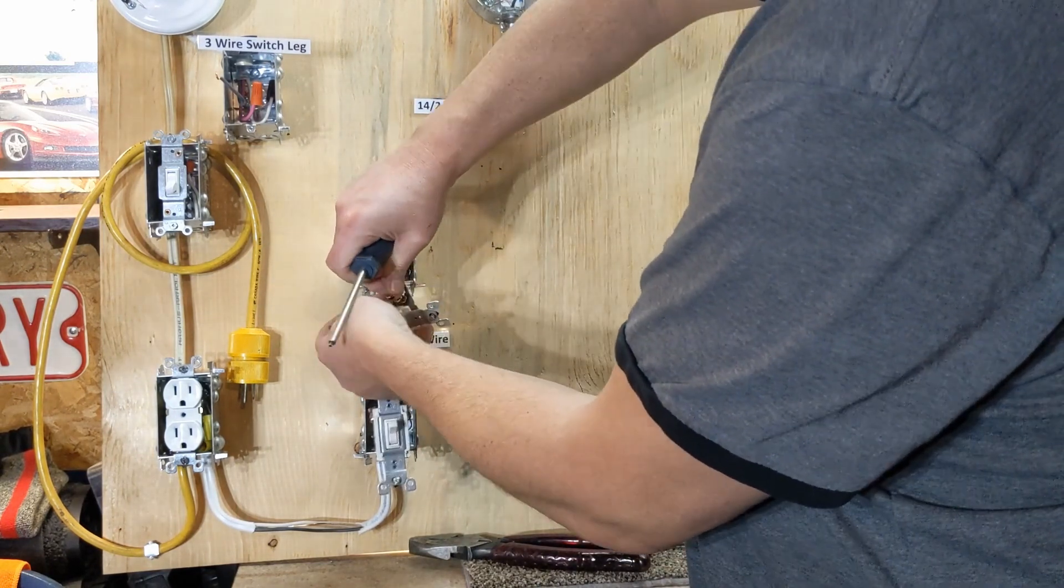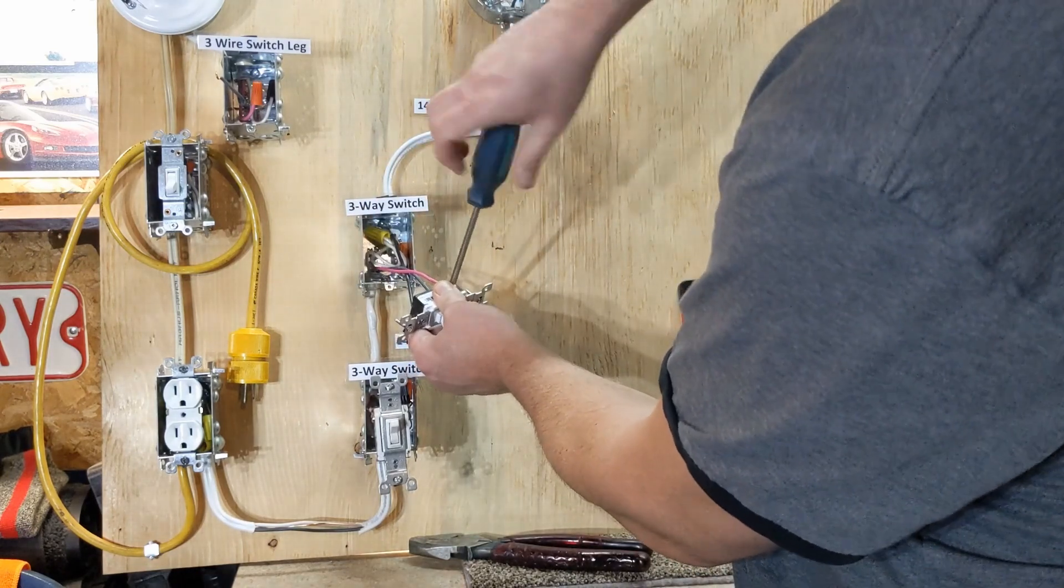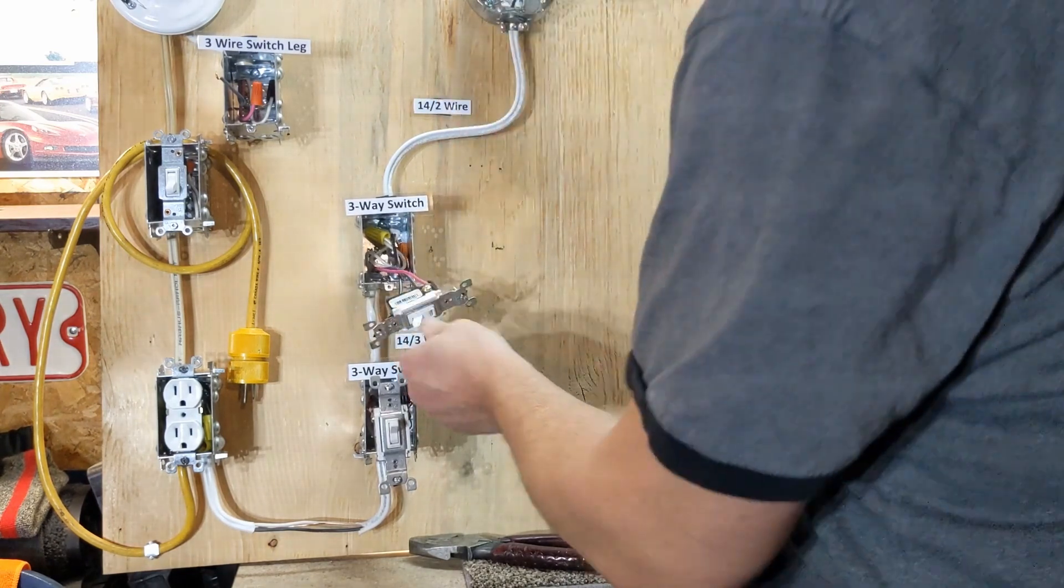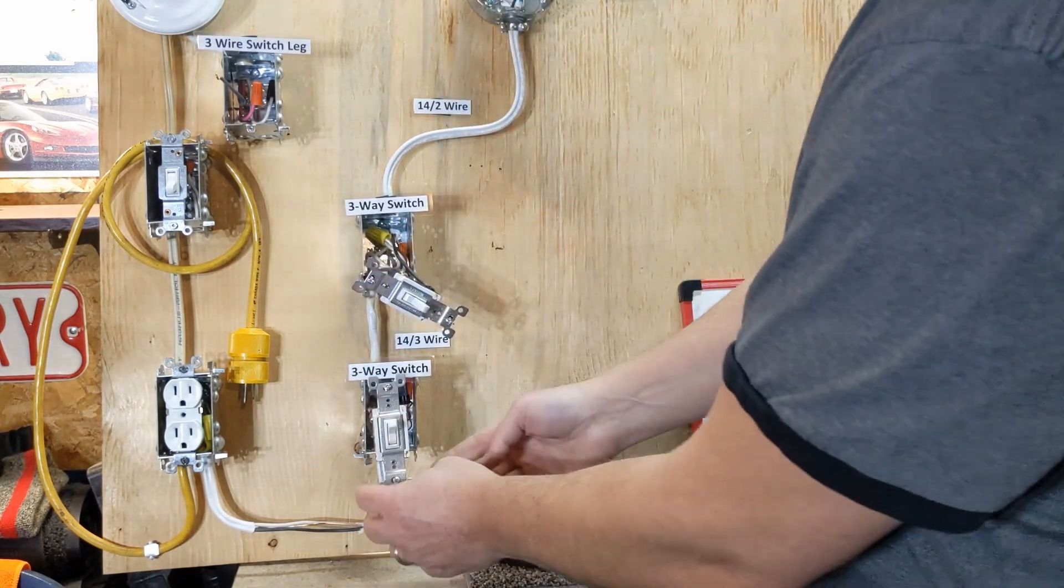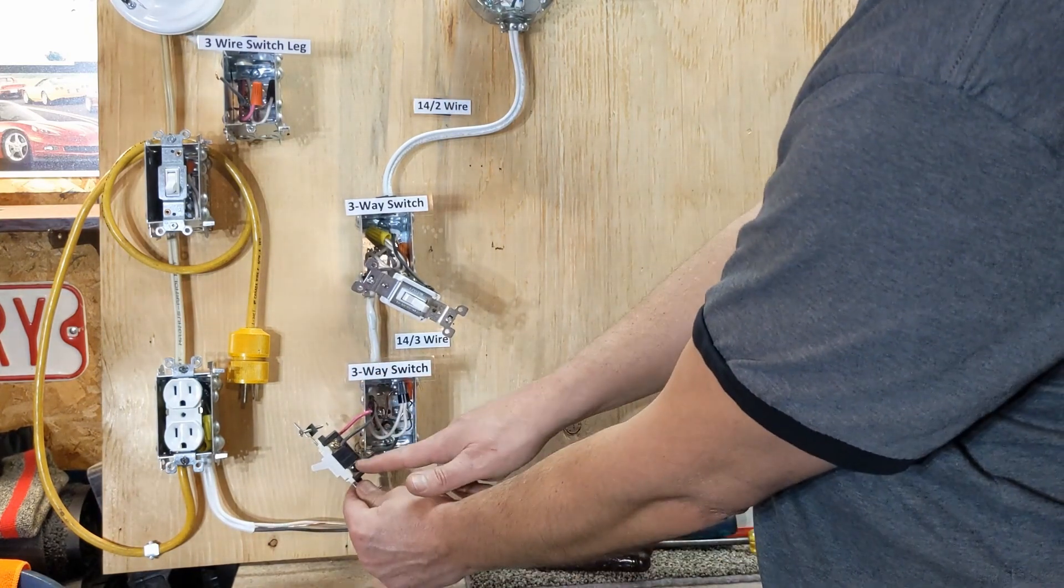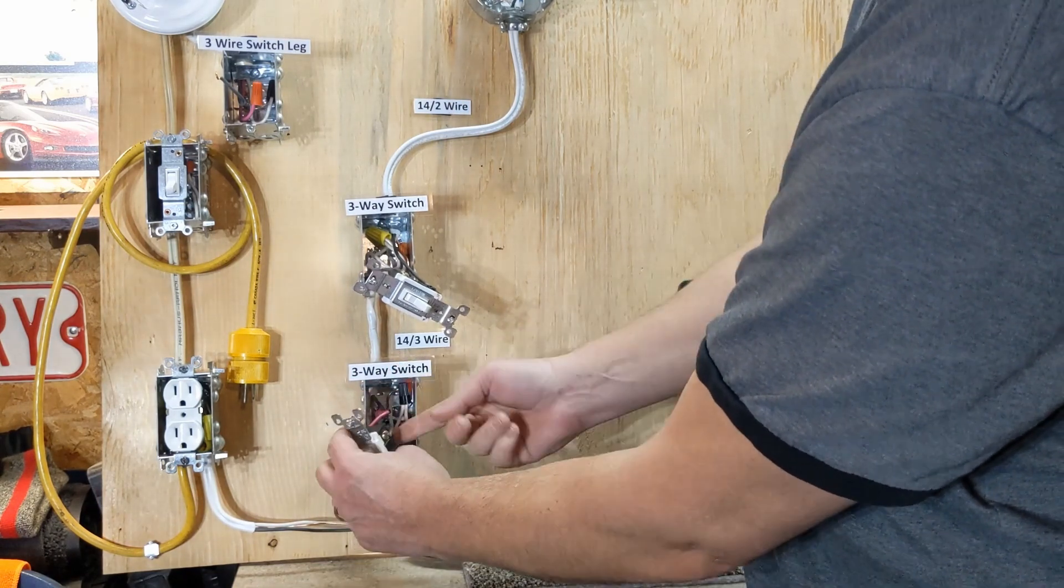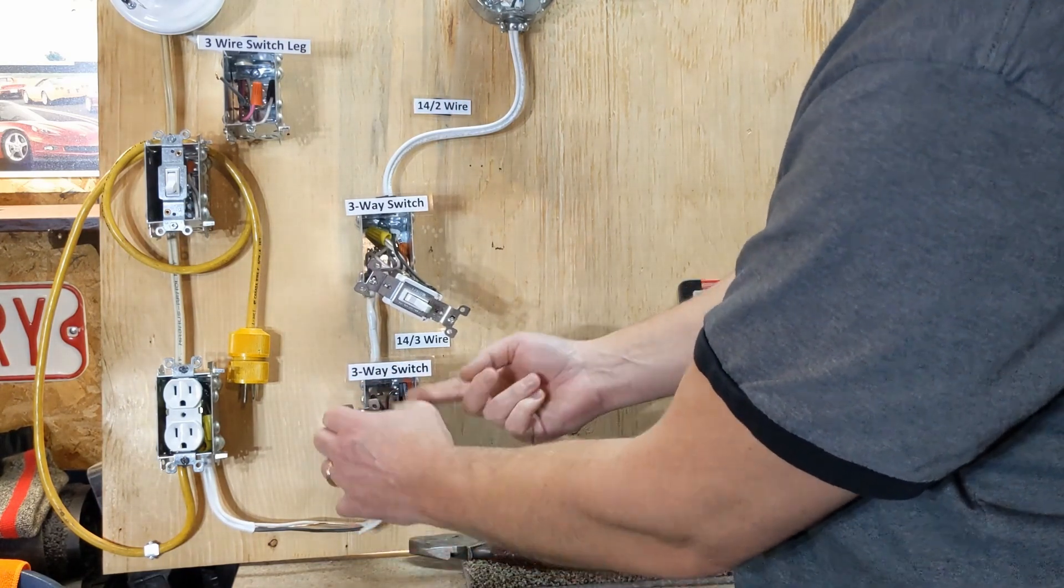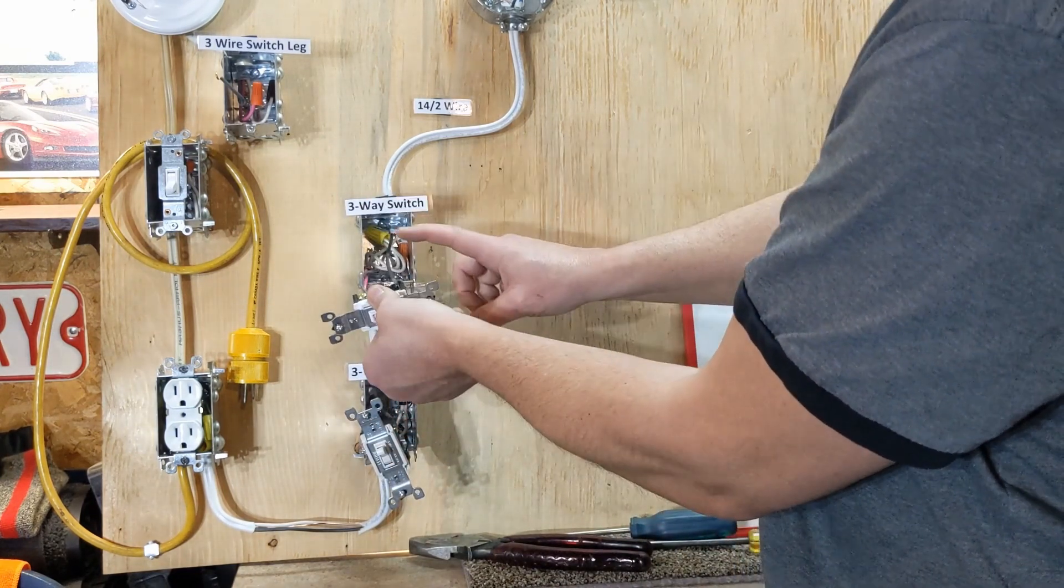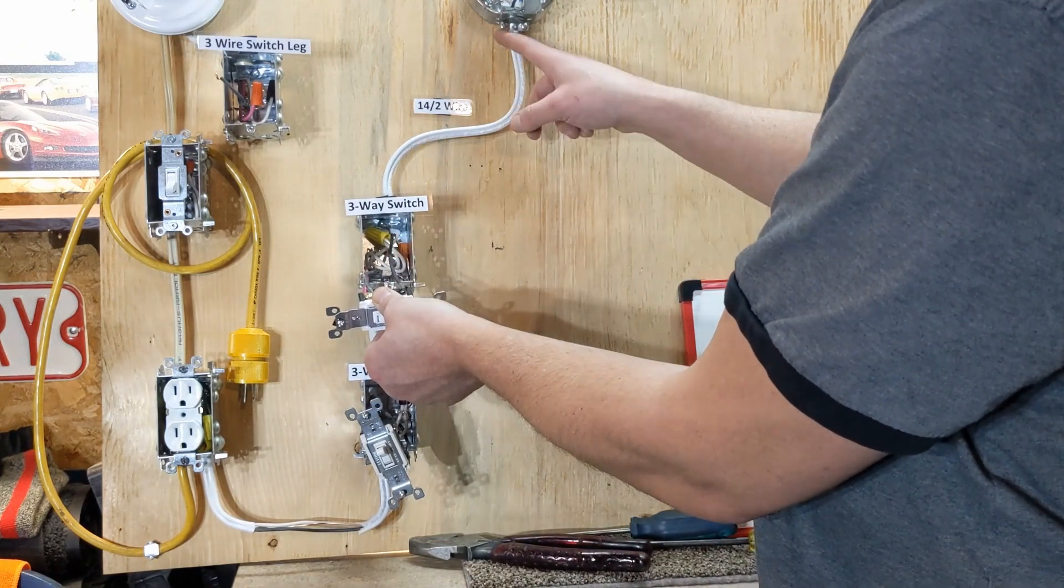One more, I'll show you what we did here and go over it one quick time and then I'll put it all together and see it in practice. So again, power coming in goes to our bottom screw. Our two travelers are the red and black coming up. Red and black on the other end go in as travelers, and then our hot leaving goes up to our light.